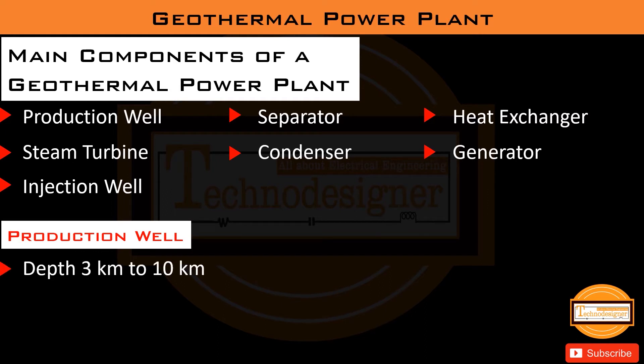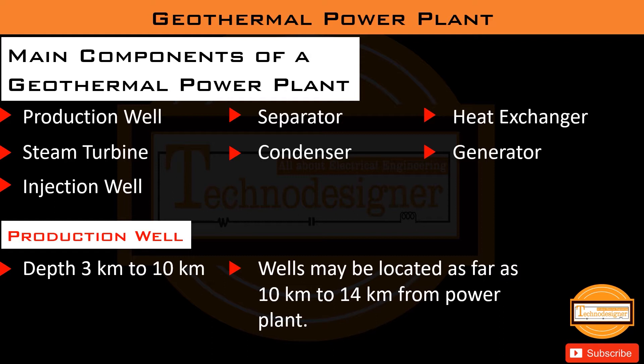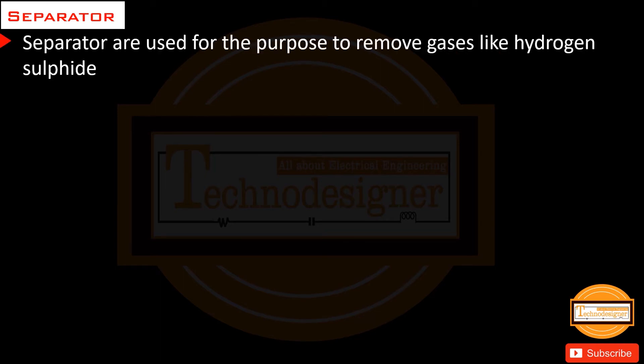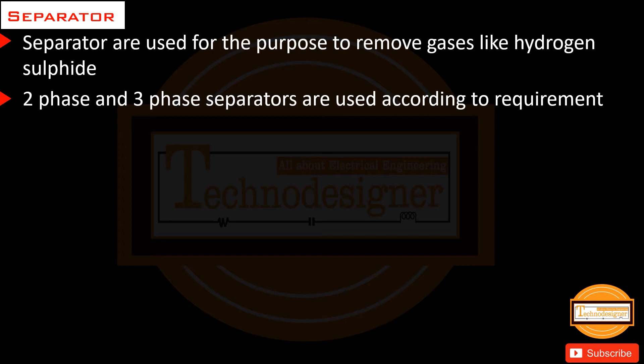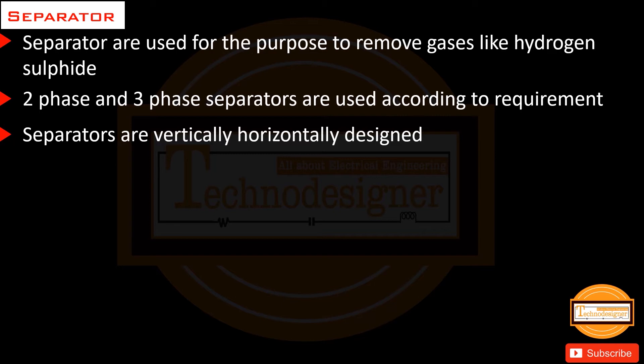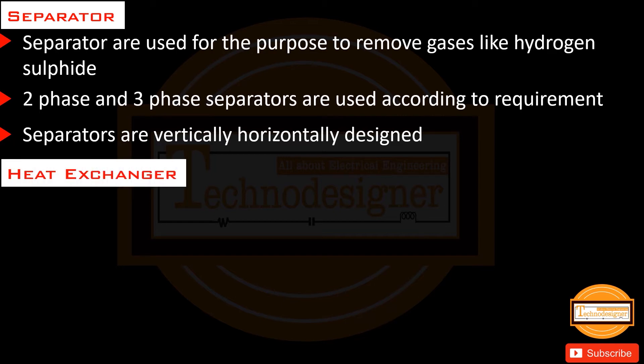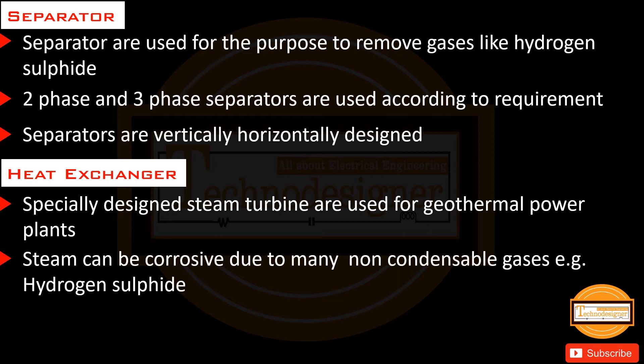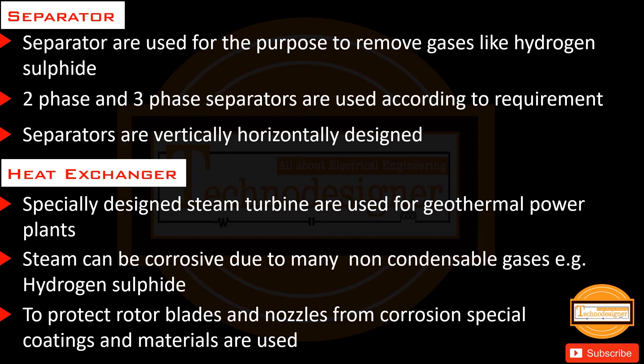The depth of a production well is from 3 km to 10 km, and wells may be located as far as 10 to 14 km from the power plant. Separators are used to remove gases like hydrogen sulfide; 2-phase and 3-phase separators are used according to requirement, and they are designed both vertically and horizontally. Specially designed steam turbines are used for geothermal power plants, as steam can be corrosive due to non-condensable gases such as hydrogen sulfide, requiring special coatings and materials on rotor blades and nozzles.